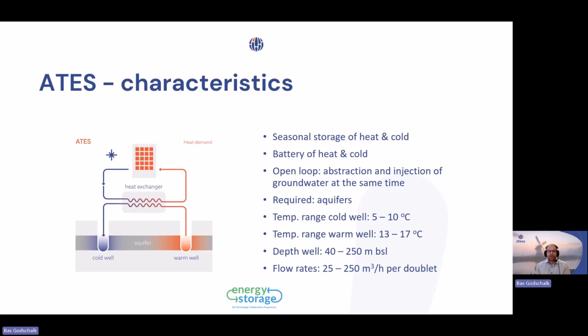It's a battery of heat and cold. In winter, when we need more heat, we abstract warm water from the warm well, use a heat exchanger to exchange the heat, use it for heating, and then the cold from the building is captured and stored in the cold well. During summertime, we reverse the pumping direction: we abstract cold water, cool down the building, and store the extracted heat in the warm well.